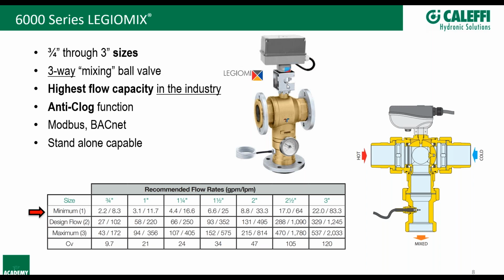Yeah, Cody, I have an interesting question here that I don't think I've ever really thought about: do we need to maintain a temperature differential between the tank and the mixed temperature so that the valve can mix the temperature? It's a great question. We do not have a minimum temperature difference from hot inlet to mixed outlet. This is something that you're going to see on every single thermostatic mixing valve, though. I talked earlier about how thermostatic mixing valves cannot completely close off the hot or the cold inlet, and that's the reasoning behind that temperature difference from hot inlet to mixed outlet.